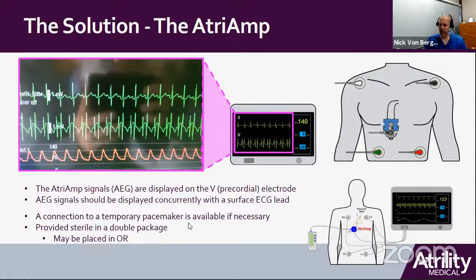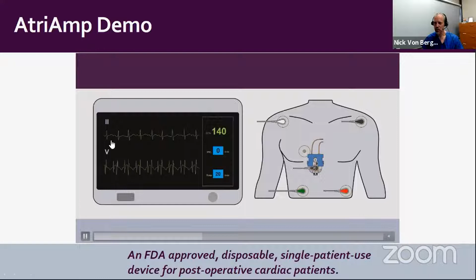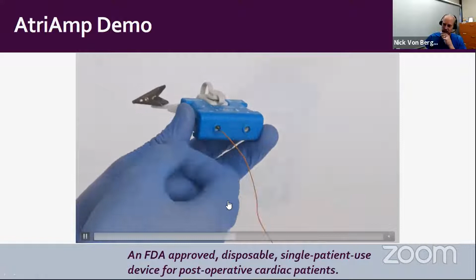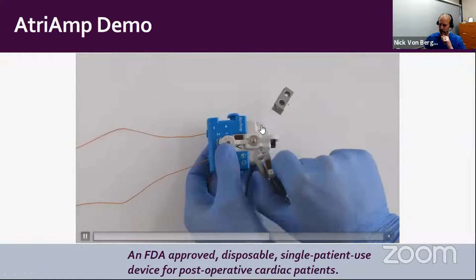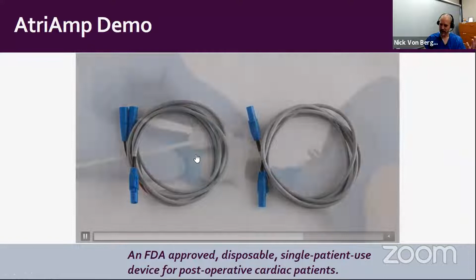So you adapt the precordial lead, you hook it up to the AtriAmp, it has a little snap electrode here. We now are displaying continuously in real time the highest quality signal with the atrial electrogram as recommended by the American Heart Association. We do this with the surface electrogram to avoid interpretation errors. To set this up, you place the epicardial wire in the negative port, and then another one in the positive port, and then you use the clip electrode, and we are now displaying. Very easy setup. And then once again, if you need to connect to a temporary pacemaker, there is a separately provided cable, and you just hook it together like this.